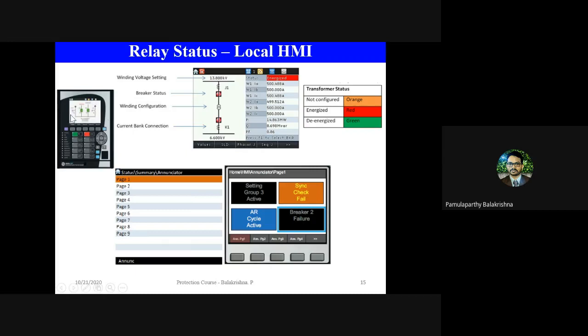HMI, which is known as the local HMI, is an LCD screen where an operator, when he is standing in front of this device in the field, can see the line diagram of the circuit, like a transformer, motor or generator. He can see various electrical data. He can see whether the transformer is energized or de-energized, or whether the transformer is not connected to the relay at all.